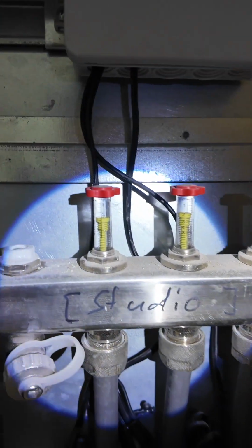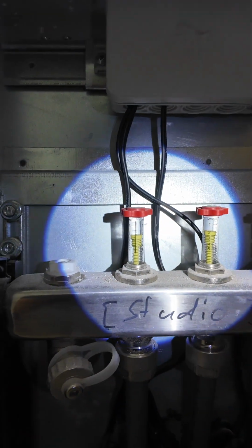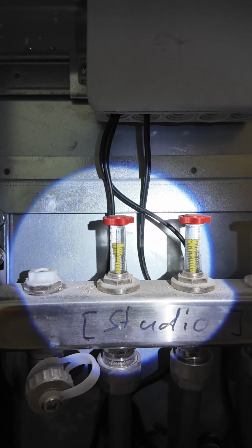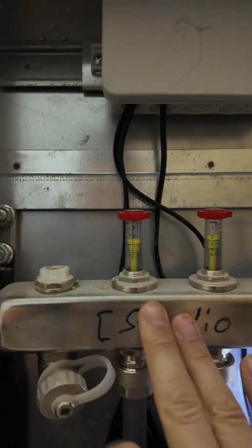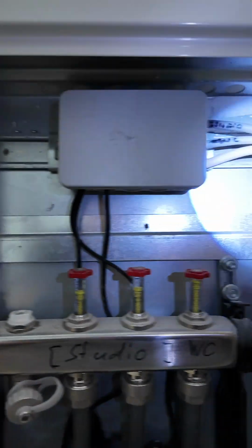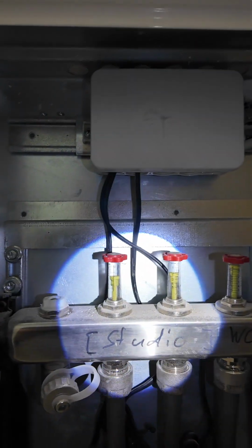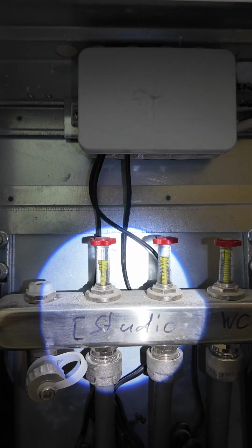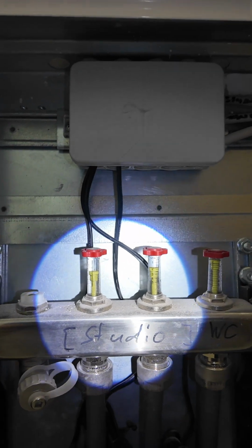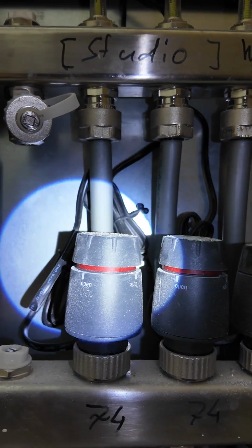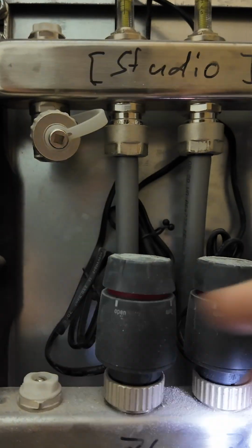You can see that in the bedroom, we've actually got water flowing through the circuit, and it's a little bit warm. What that means is, because the thermostat is turned on to a value of 3, we are actually sending hot water through the circuit. And you can see that these valves are open up a little bit too. Do you see that? You can see this red ring right there.